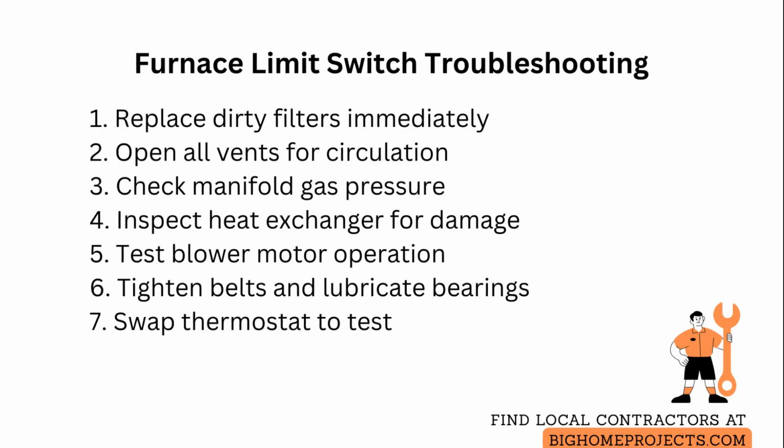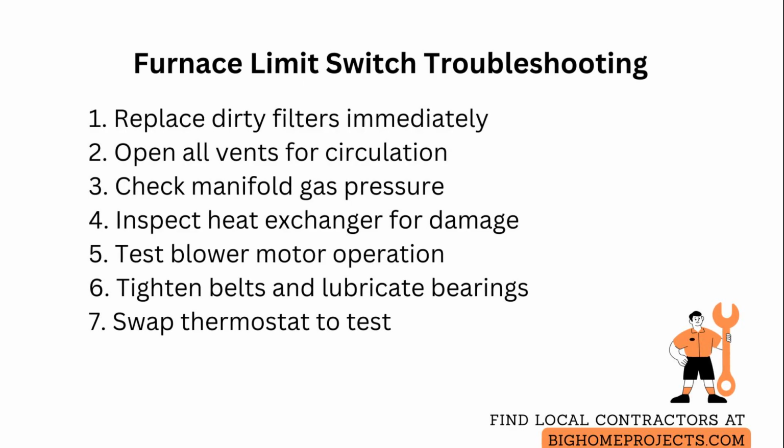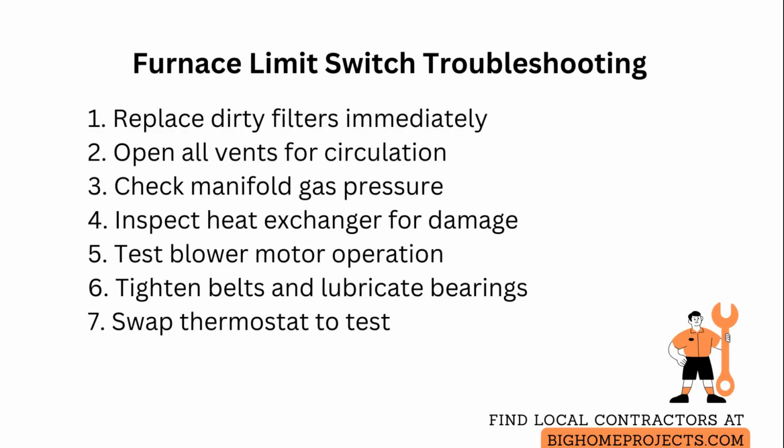Motor or blower failures reduce airflow. Test the blower by turning the fan to on and listening for steady operation. Tighten loose belts and lubricate bearings if applicable, or replace the motor if it does not reach rated speed.